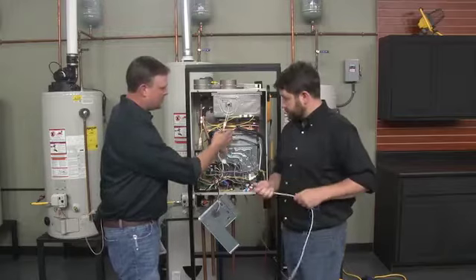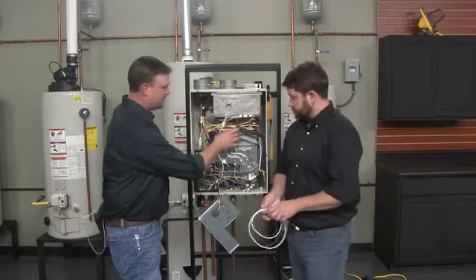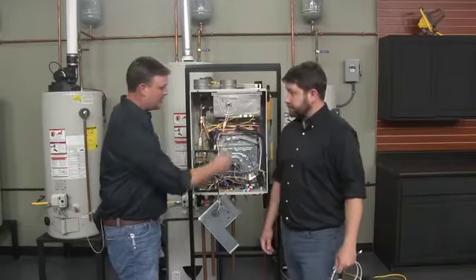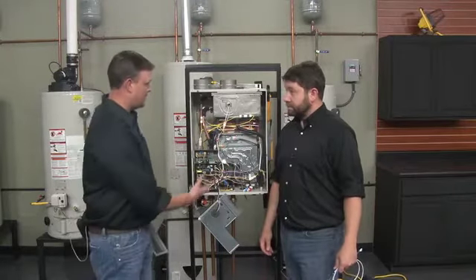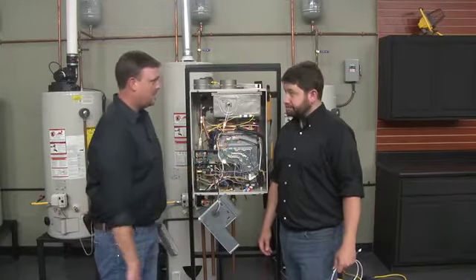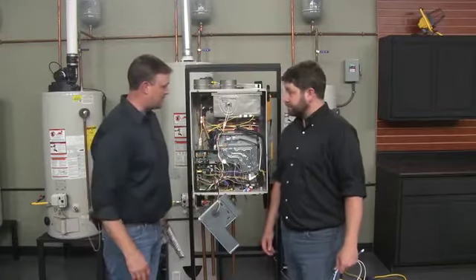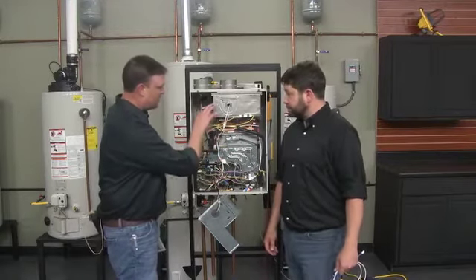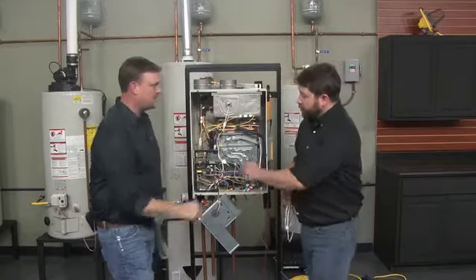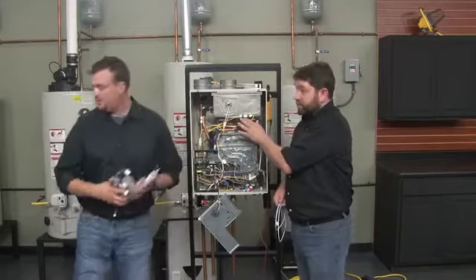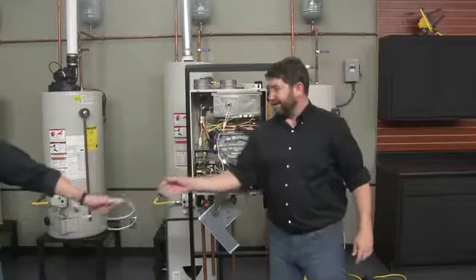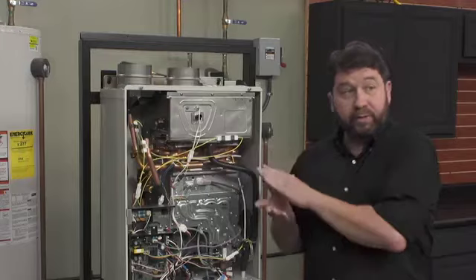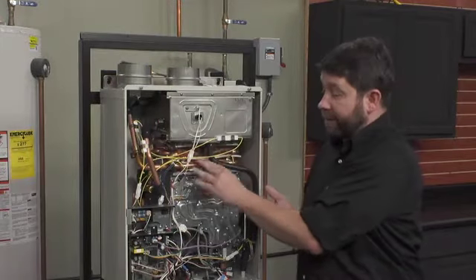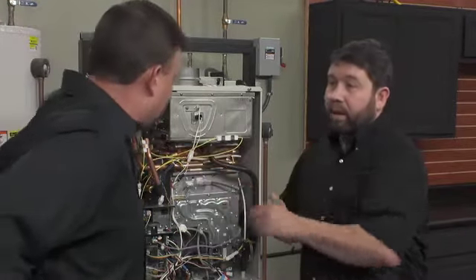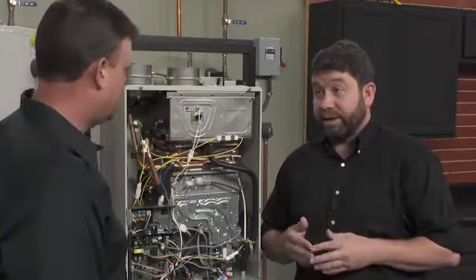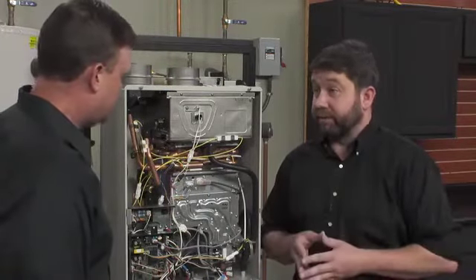Also, there could be a bad gasket, a bad seal here, that can allow those flue gases to come up. So if you've had to take that apart for some reason, you might have to do that as well. There wouldn't be anything between the secondary heat exchanger and the primary, is there? There is a gasket in between the two heat exchangers, but where it's up above that safety fuse, probably not going to be the case. But still worthwhile to check if you don't see any other obvious signs of where the heat's come from.